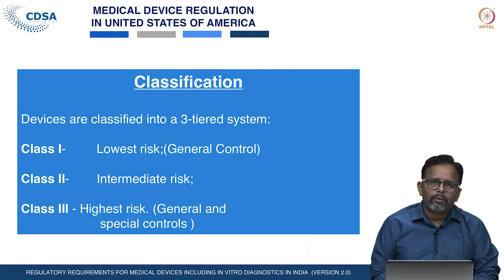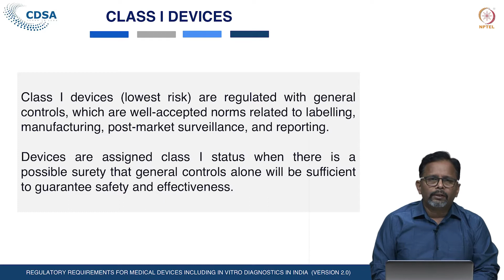Class 1 devices are the lowest risk devices in USA and they are regulated with the general controls, which are well accepted norms relating to the labeling, manufacturing, post marketing surveillance and reporting. The devices are classified as class 1 when there is a possible surety that the general controls alone will be sufficient to guarantee the safety and effectiveness of that particular device. Moreover, for class 1 devices, the countermeasures such as seizures, recall prerogative, etc., are granted to the Food and Drug Administration.